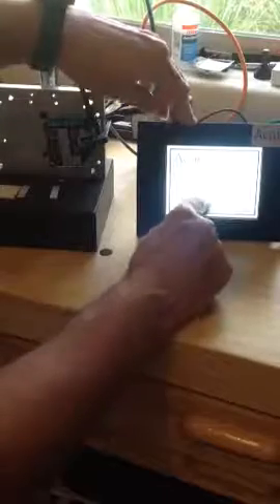And so typically the way I would usually try to correct this, I would first do a quick 2-point calibration, and we have that set up in our little touch panel where we would do just a quick 2-point cal. And so it says there's the number, that's the base material we're going to put in the gauge block. And let me just tap this down a little bit to get all the air out of it. And then we know this is 0.03937. So we've just done a quick 2-point calibration, and let's go back.